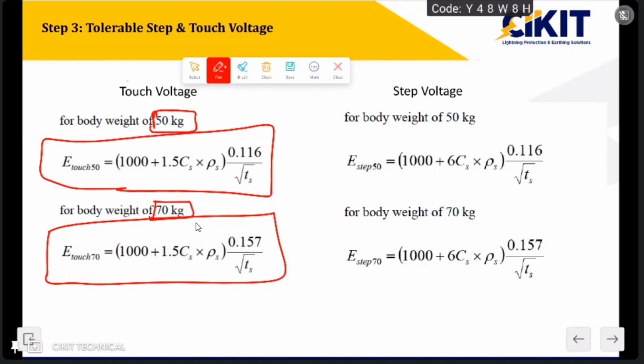So if my body weight is 70 kgs, then I can withstand a little more current. But the thing we have to consider is whether it is in our control, because the substation will be a closed environment. So we can control who can enter the substation. If we have a strict rule that only persons with a weight of 70 kgs and above will enter the substation, then we can go for this calculation with 70 kgs.